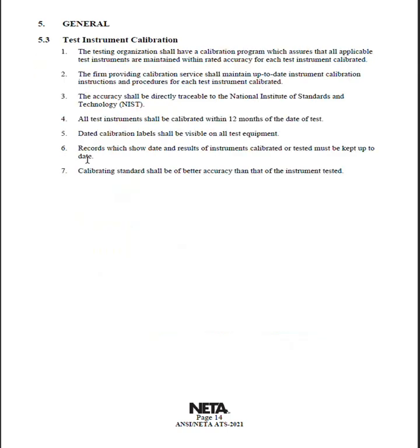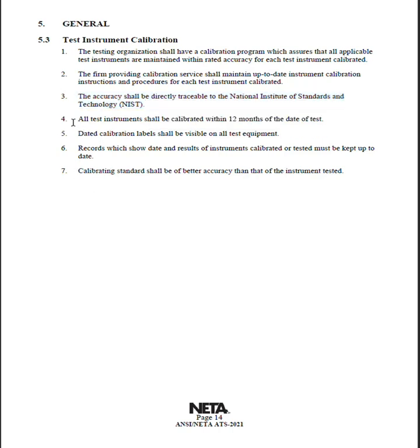That's not the point of what we're going into. And equipment calibration, right? Required to be every 12 months and NIST certified. 12 months right here and NIST certified. Okay. Must be traceable. If the customer says 6 months, fine, they're paying the bills. 6 months is still within 12 months, right? That means you're still making it every 12 months.